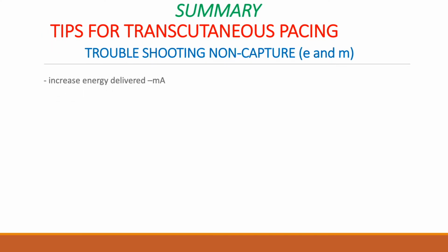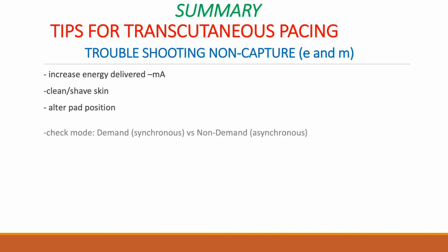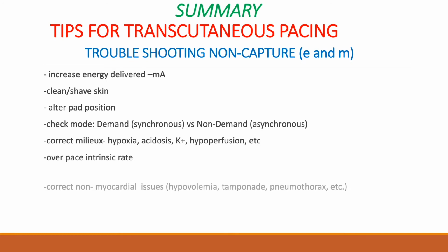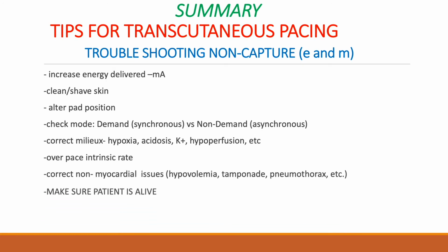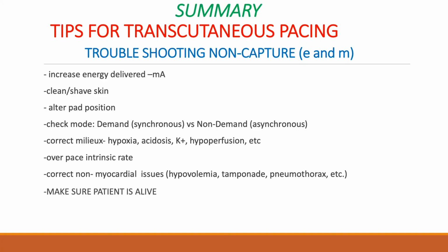What else can we do if you're having non-capture with either electrical or mechanical? Obviously, we can increase the power output, make sure that the pads are in good position and working well, and make sure whether you're in demand or non-demand. You have to correct the other problems. If they're hypoxic, if they're really acidotic, you've got to correct those before this is going to have a chance to work. This rarely happens, but obviously you've got to pace them faster than their own intrinsic rate. And we already talked about correcting the non-myocardial issues.